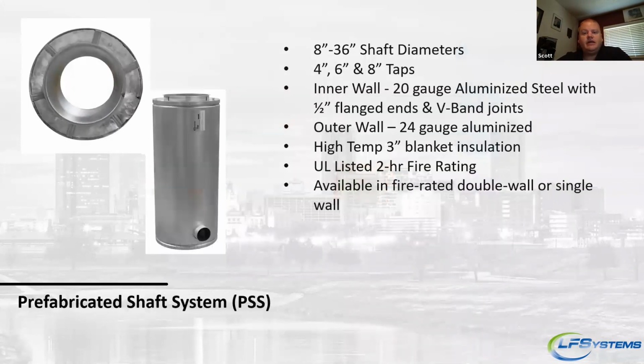Now, on a side note, we do offer a prefabricated shaft system. This is a UL-listed 2-hour fire-rated shaft. It is a flange-to-flange connection. If you're familiar with boiler flue, it goes together the same way. Flange-to-flange connection with V-bands. It's a plug-and-play system. It has taps already built in from the factory at designated points. And basically, you can stack this any way you want it.